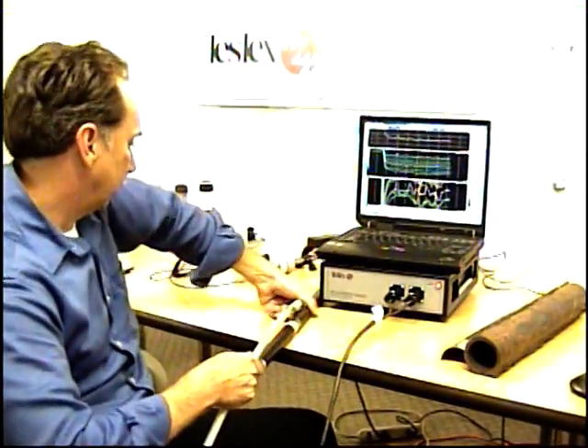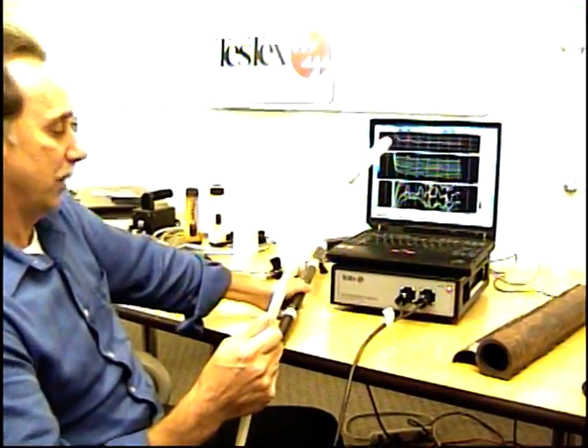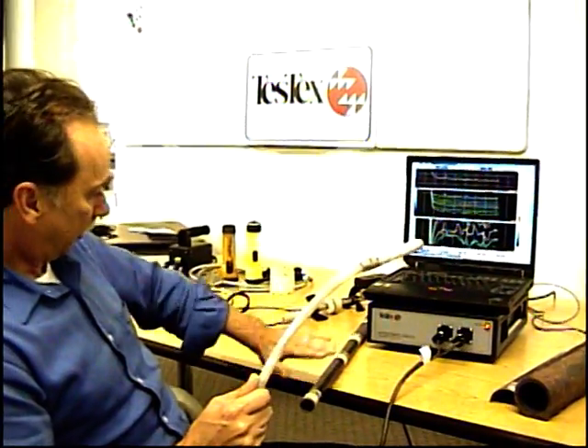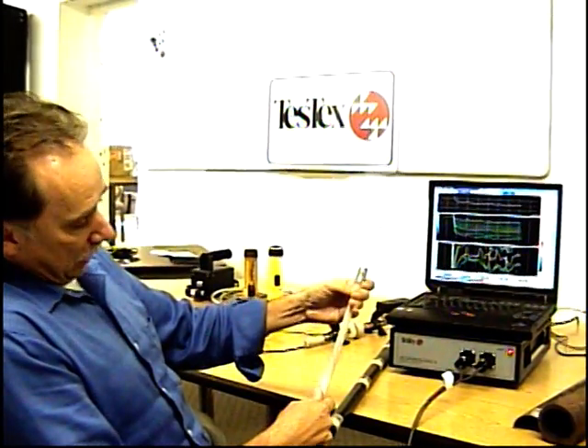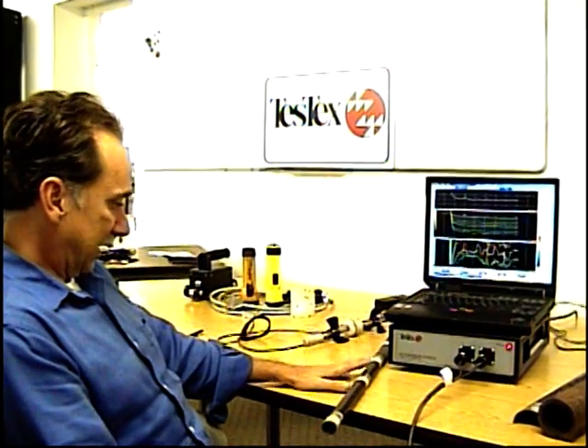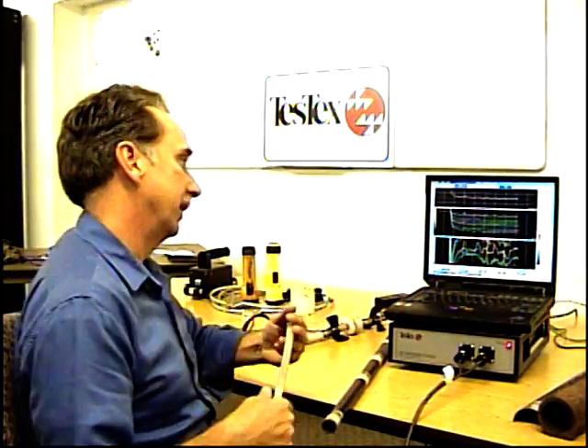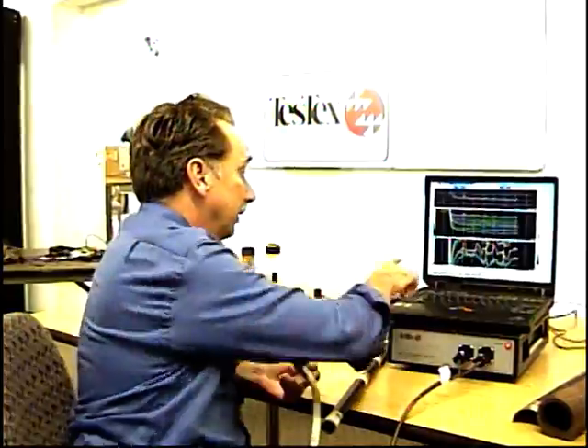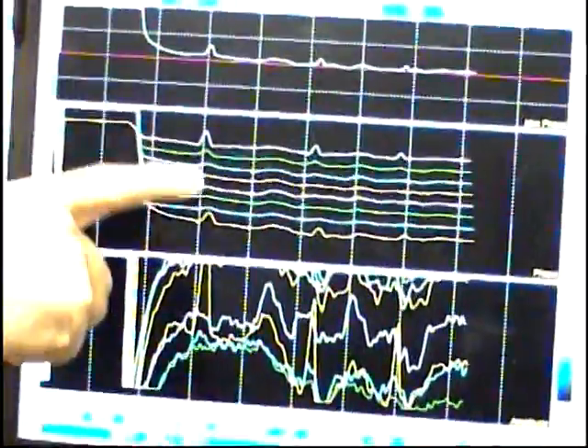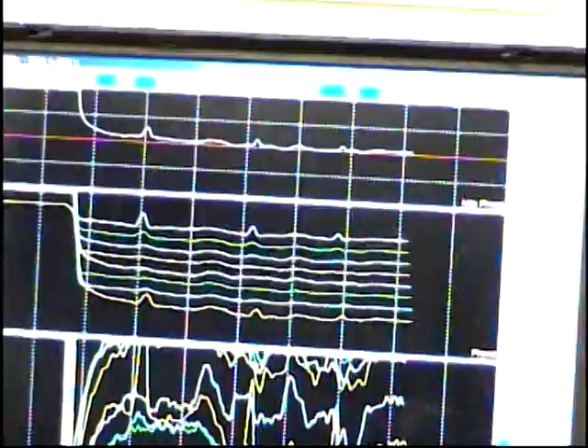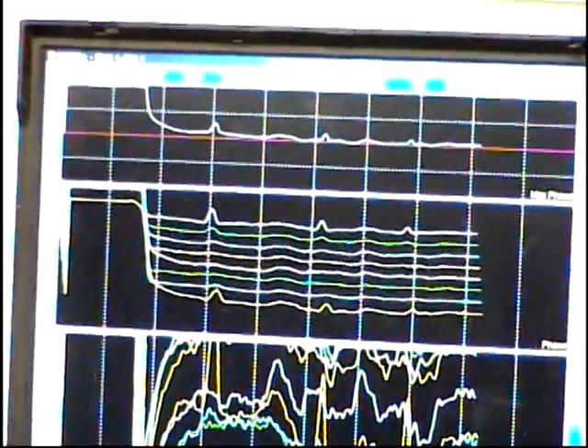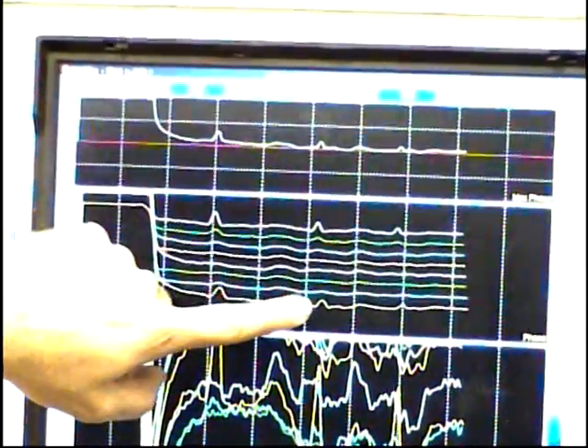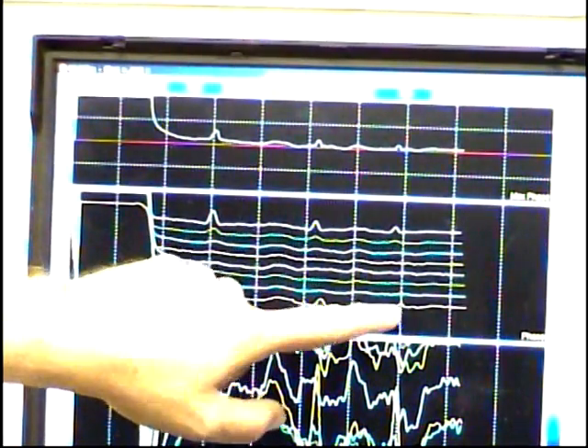We can actually go back and, by measuring the probe in the tube where the flaw is at, we can give an approximation of from the tube sheet back, how far back in the tube it is. But again, we can't distinguish between ID and OD flaws. Now with eddy current you can do that, but that's for a different demonstration. Now you're going to notice here, if you look, you got three different views here, or three different pits. Again, this is the 92% pit, 76%, and the 58% pit.